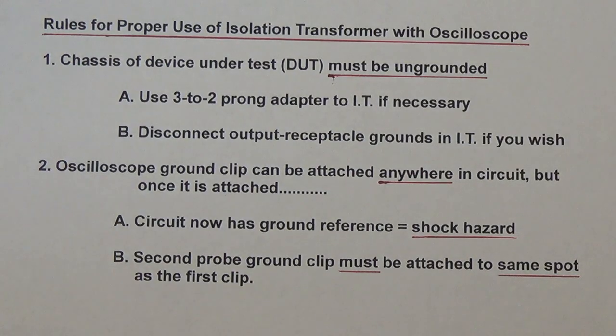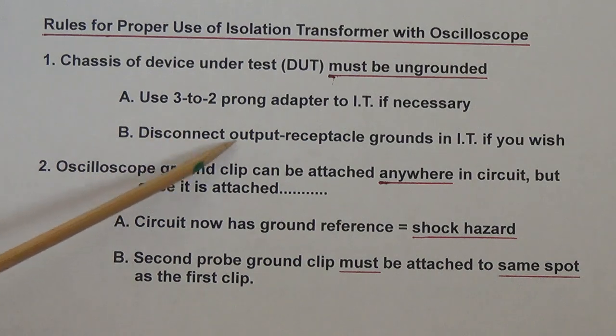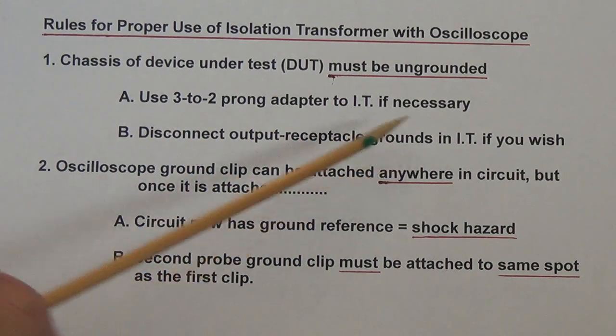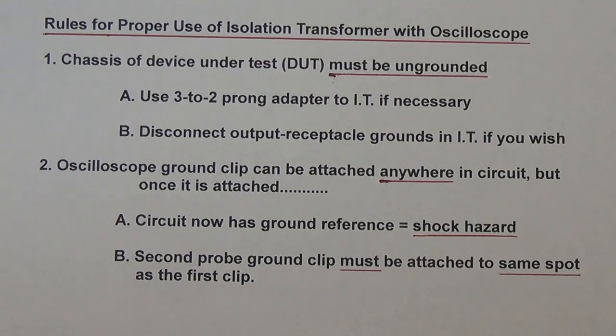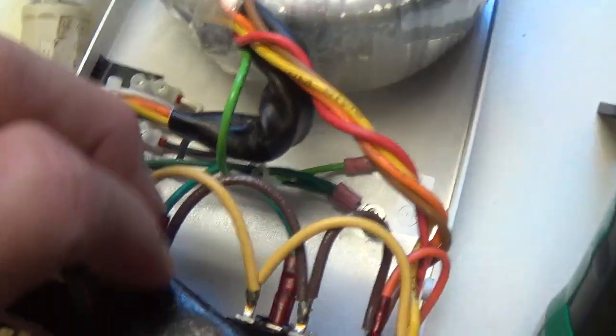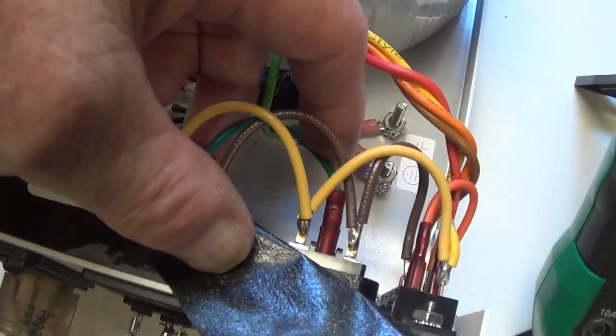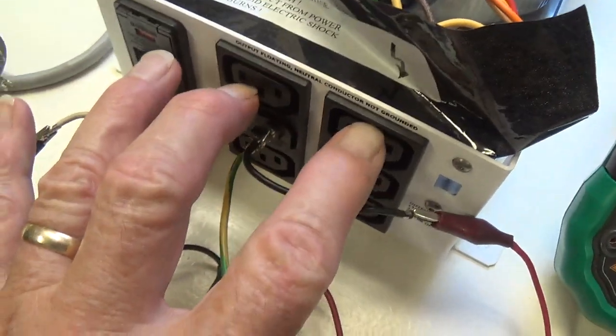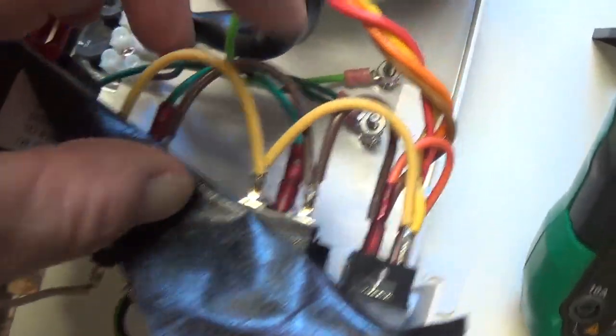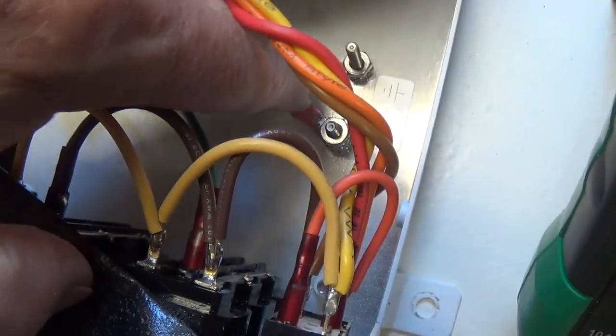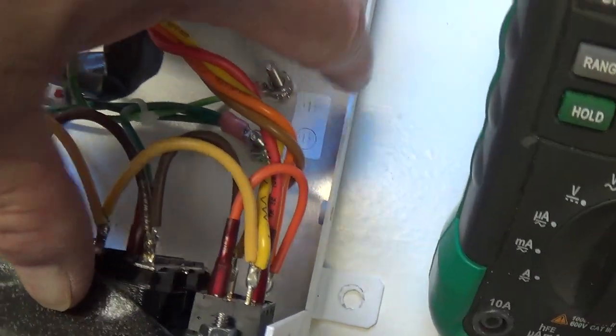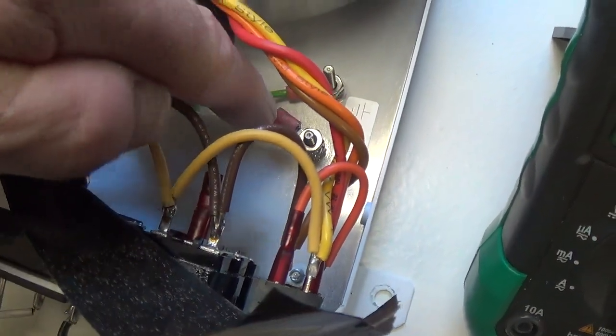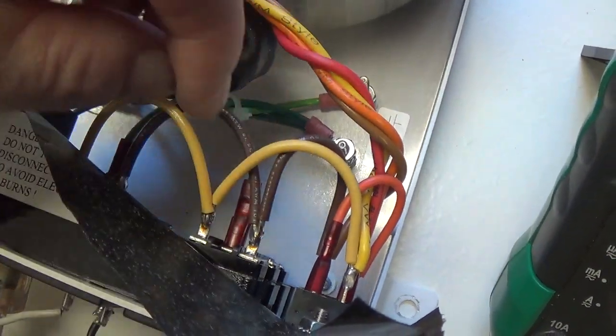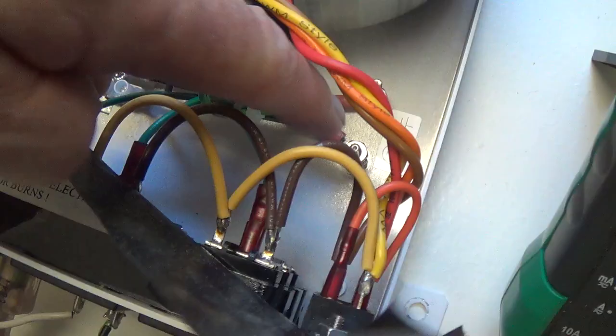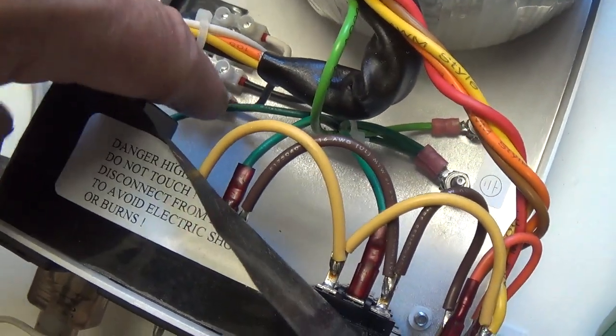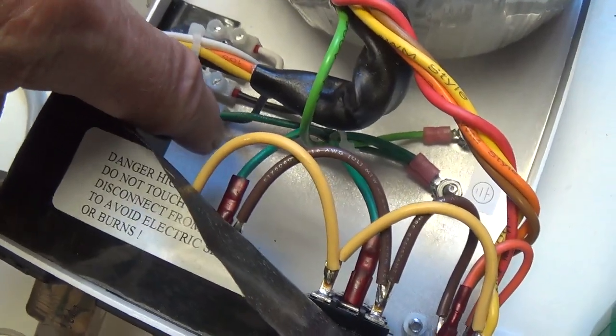Or, if you don't like using adapters, you can permanently disconnect the output receptacle grounds in the isolation transformer if you wish. In that case, you'll have to go inside and find the 2 green wires which provide the grounding to your output receptacles. Trace them all the way down to the floor where they're bolted down here to the chassis ground. Unscrew the nut, remove the 2 of them, tape them off, curl them up so they're out of harm's way, and then tighten that nut back down on the power cord ground, which you will leave intact.